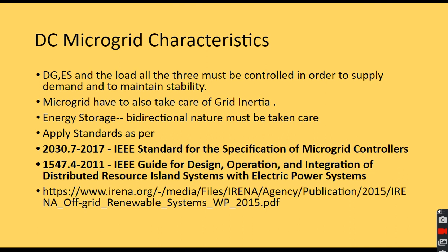It has to get the power and give back the power. Next, it has to automatically handle load shedding if the load is higher. If the load is higher and the battery is able to supply, then the battery has to supply. ES, that is energy storage, is the battery. When the distributed generator (DG) is powering higher power it can generate, then you don't need a battery. So this decision making must be taken care of by the DC microgrid.